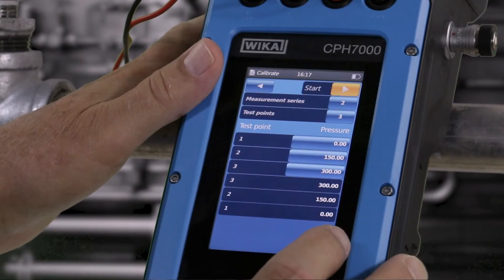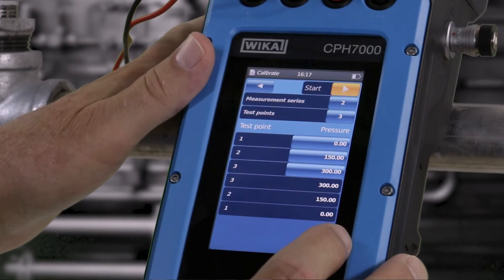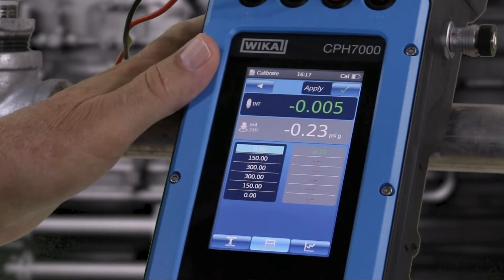Press start. If your calibration begins at zero gauge pressure, make sure the vent valve is open to atmosphere. When the zero point is stable, press the apply check mark. This records the reading.